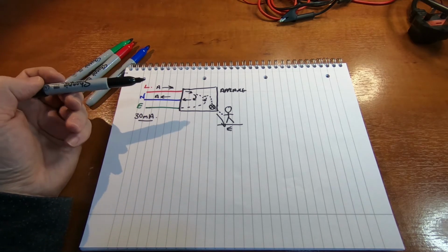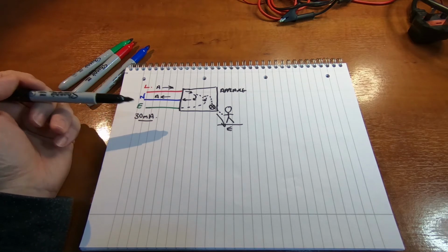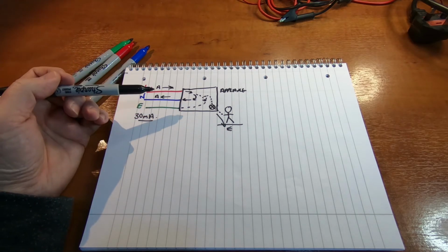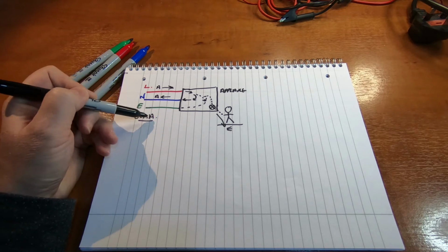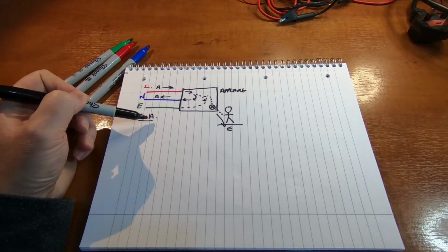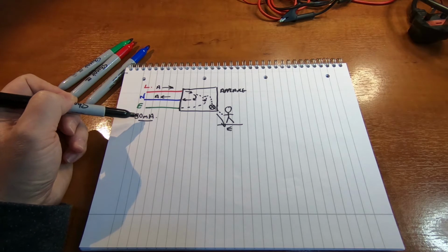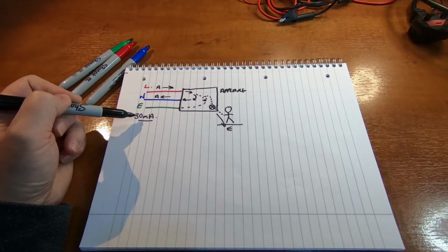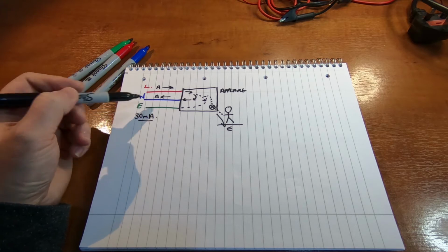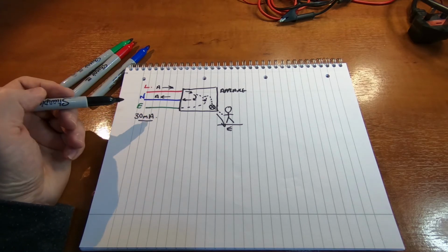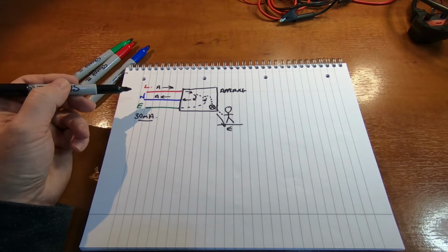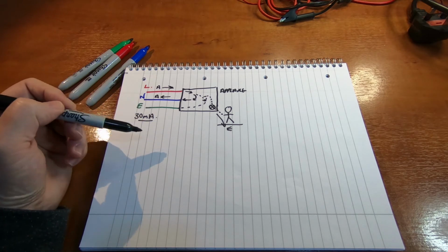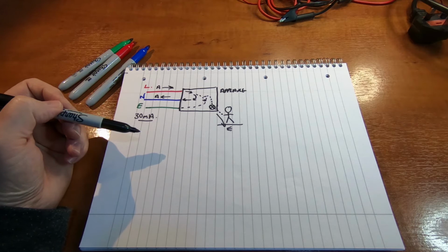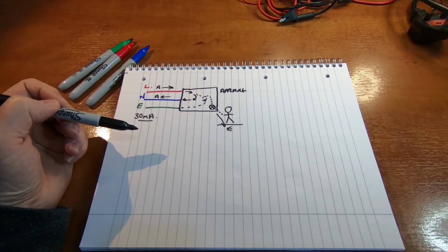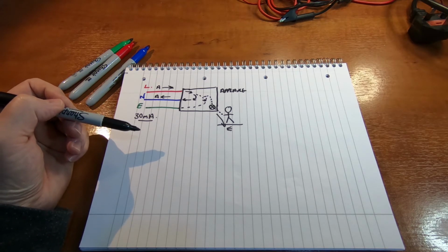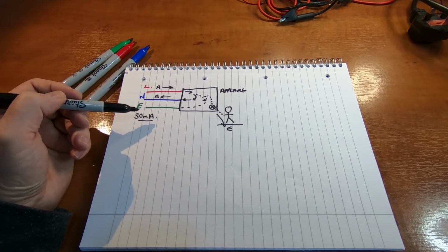So it's a question of going around the house, unplugging all your appliances, seeing if it happens. But if it's intermittent, again, it's difficult to trace. So you could have maybe 3 devices, and each of those have a 10 milliamp earth leakage. But combined, when they're all plugged in, you get the 30 milliamps or more, and it'll trip the system. So what I'm hoping to do is to create a device here which we can individually plug our appliances into and check them out. So if we were suspicious of a device, a kettle, steam iron, whatever, we could plug that in and measure the earth leakage.